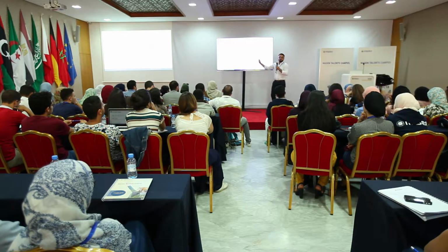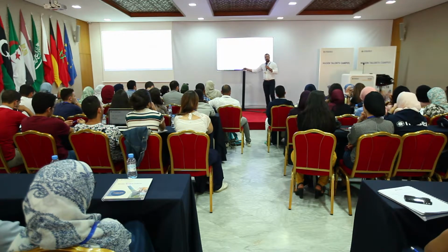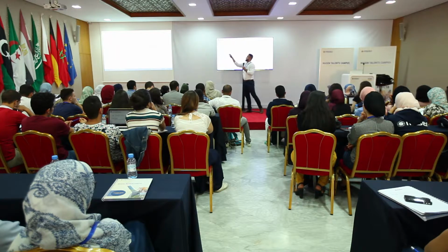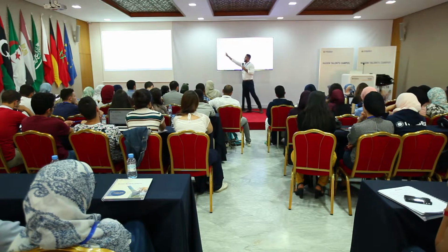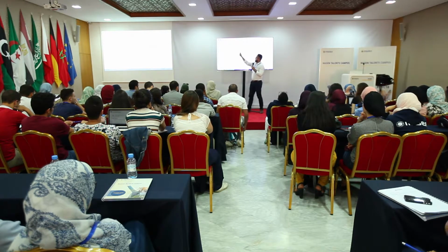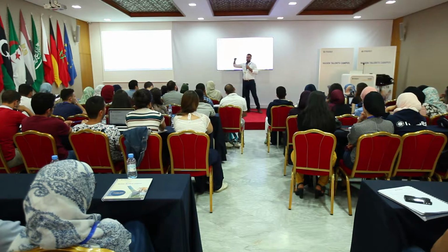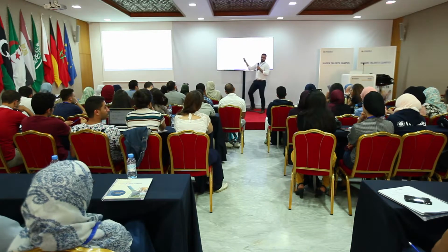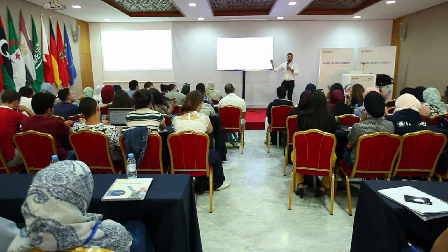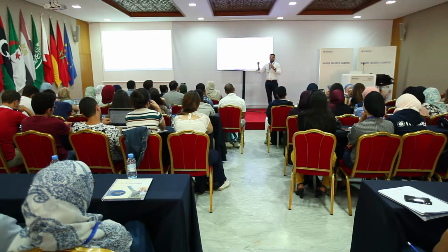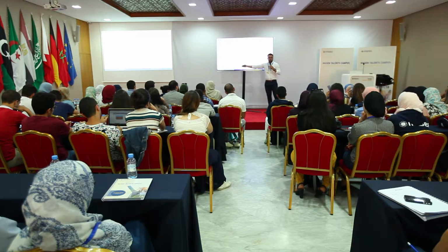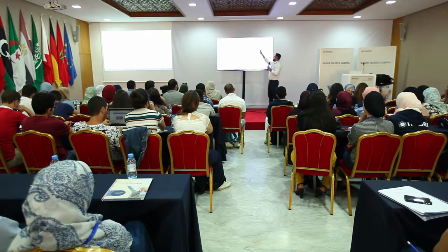And then with those inputs, you have a model process where you size the plant, and that's done at a specific design point, which, coming back to the beginning of the lecture today, can be solar noon at the equinox. So for that specific time, I assume an irradiance of 850 watts per meter squared, and I consider a solar multiple of, whatever the design is, say 2, and a tower of 180, whatever. I size everything and calculate my whole plant.